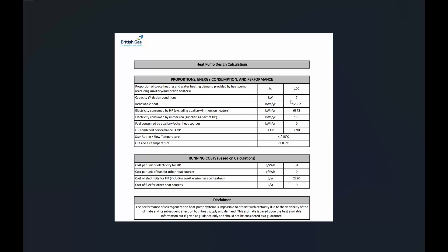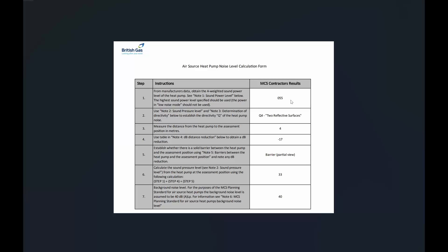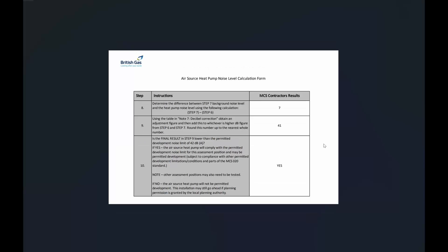Noise level calculation form. One of the main reasons that we had to go for the Vaillant was, although I ended up getting planning permission anyway, the Vaillant one passed the MCS noise level calculation and the Daikin that they were originally proposing did not. There was a few decibels in it but ultimately they wanted it to be lower than 42 I believe and this one comes out of 41 using the Vaillant figures.